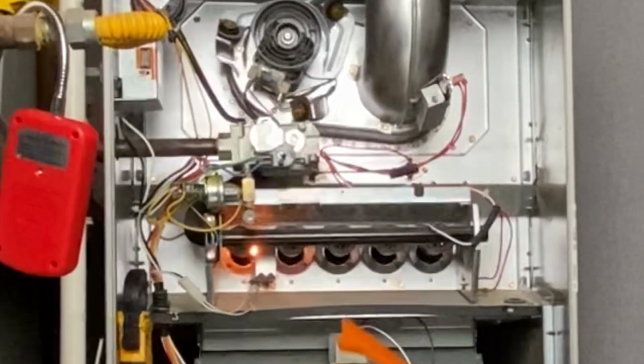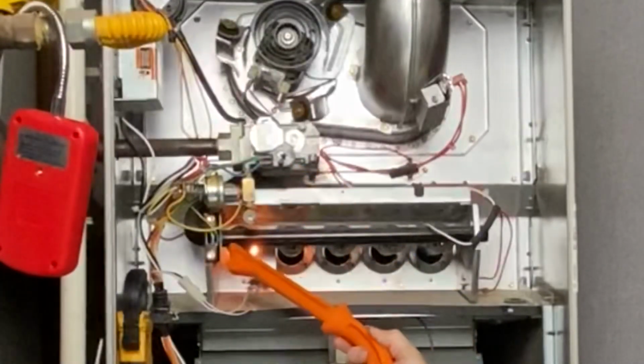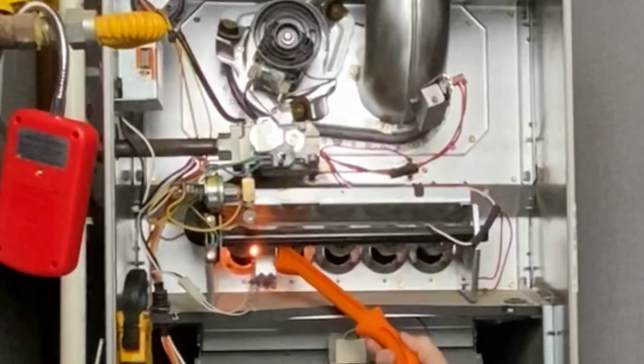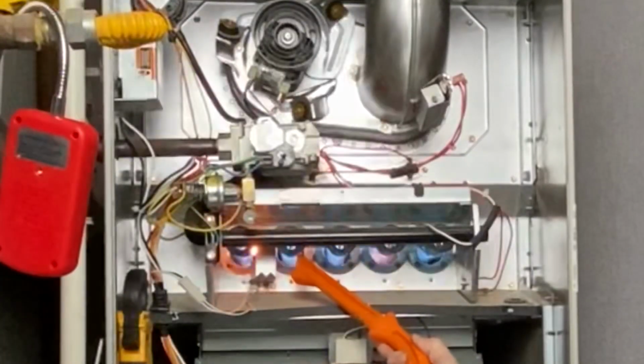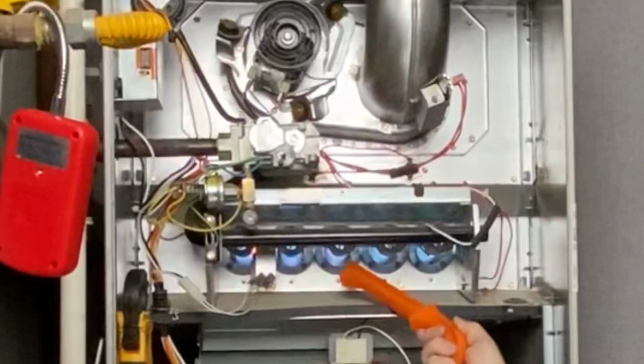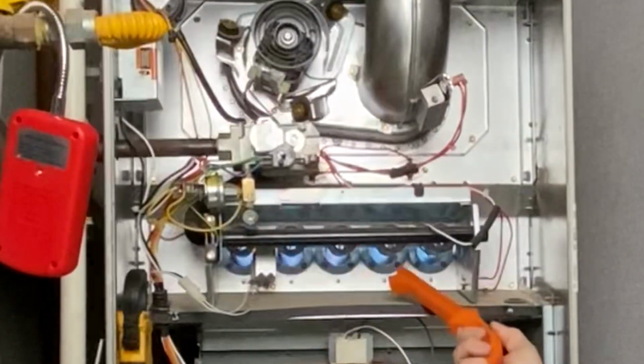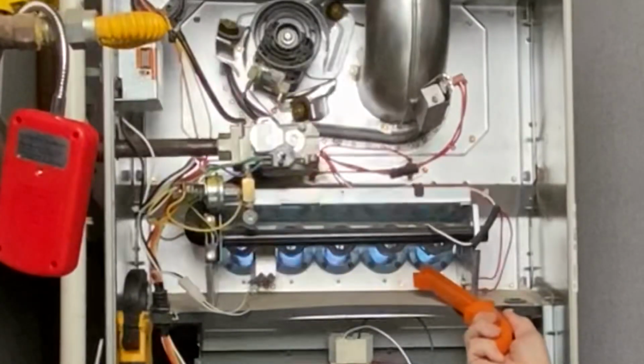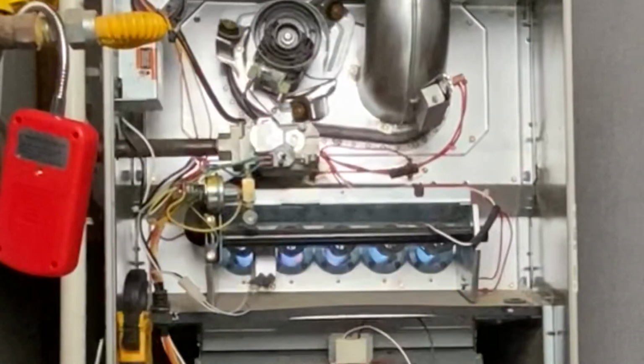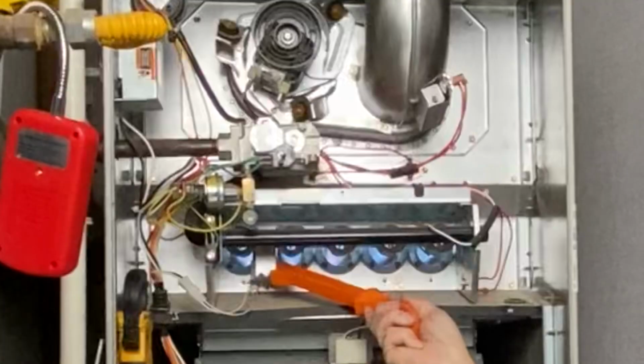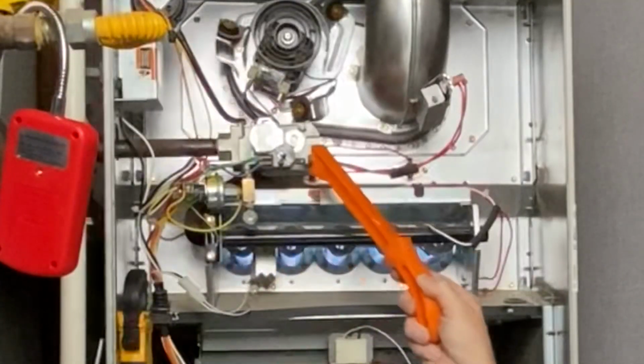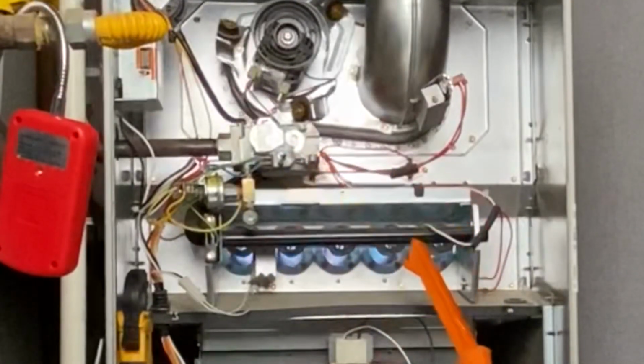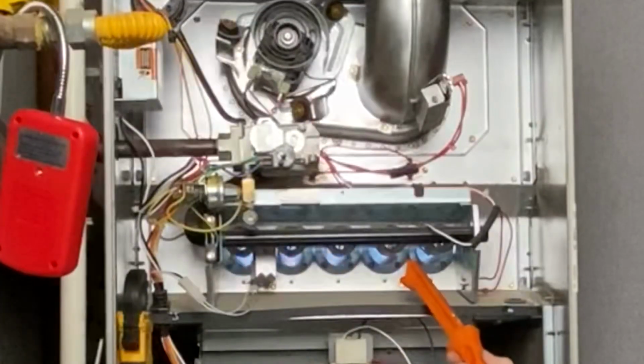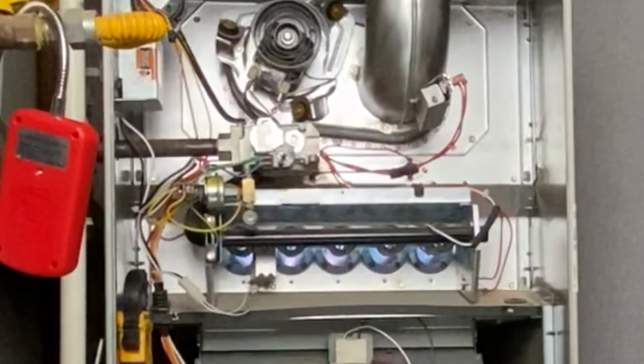Then the IFC is going to energize the combination gas valve, allowing gas to flow through the manifold, to the spud, through the orifice, mixing with primary air inside the burners, igniting into a flame burning inside that heat exchanger. That flame sensor has a few seconds to prove a flame through a process called flame rectification. Once the flame's proven, the IFC shuts off the hot surface igniter because we don't need it anymore. The IFC keeps the combination gas valve open so the gas continues to flow. The IFC is going to let those flames heat up that heat exchanger. Then it energizes the blower motor and starts moving air into the house.